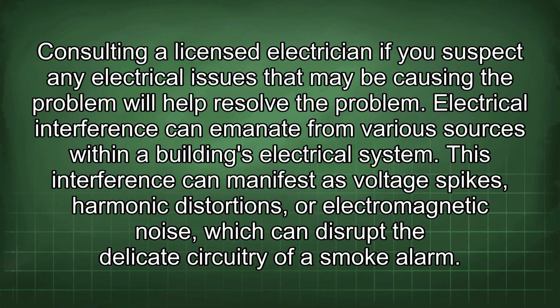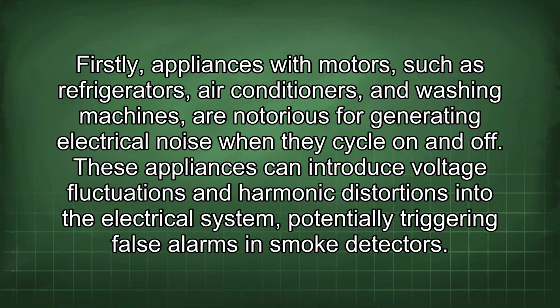smoke alarm. Firstly, appliances with motors, such as refrigerators, air conditioners, and washing machines, are notorious for generating electrical noise when they cycle on and off. These appliances can introduce voltage fluctuations and harmonic distortions into the electrical system, potentially triggering false alarms in smoke detectors.